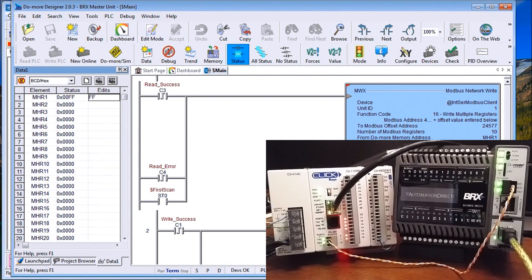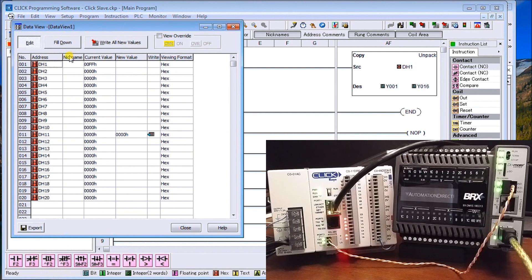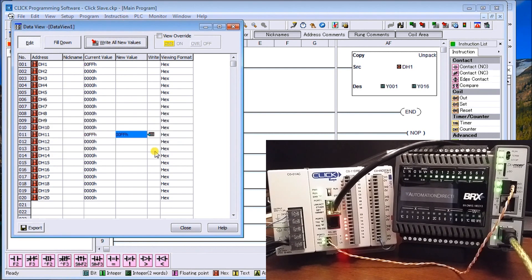Now let's make sure we're communicating the other way. Calling up the Click software and data view, you can see where the FF value is coming from our BRX. We'll modify DH11 and put the value of 1 in and write it — sure enough, on our BRX PLC the first output is now on. Turning on the first four, then the next four — sure enough they all come on, confirming bidirectional communication.